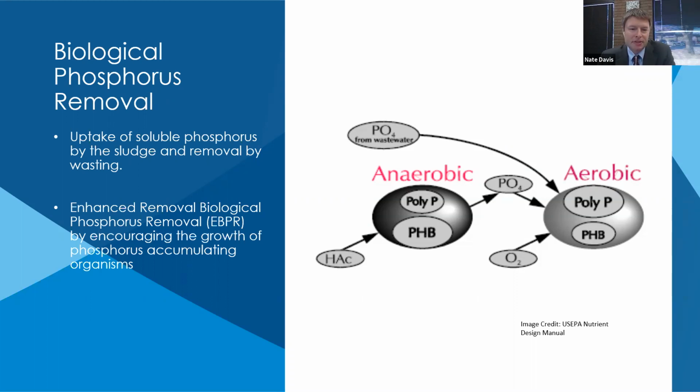They can still get by releasing stored phosphorus as an energy source. And then later, once they get into aerobic conditions out of that stressful environment, they'll uptake more phosphorus than they released and store it, in anticipation of having that stressful environment again. And that's what drives up the phosphorus content of the sludge.